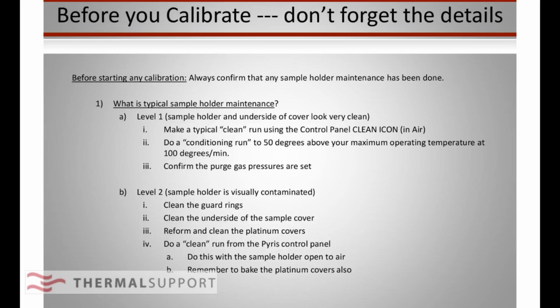You want to do a typical clean run, and you can make that a regular method where you ramp up at 100 degrees a minute and stay at, say, 600 for a few minutes, then it'll show you where contamination is coming off. If you don't want to do that, just tell it to do a clean run. When you're ready to start doing this, you also want to do a conditioning run. Make sure your baseline's in good shape, your purge gas pressures are good. That gives you a good starting point. Now, let's say you're like so many other people and you have visual contamination, and you say, all right, I really need to clean this.